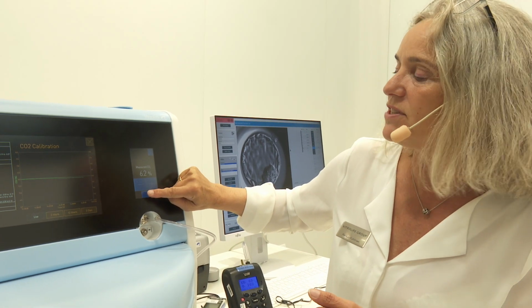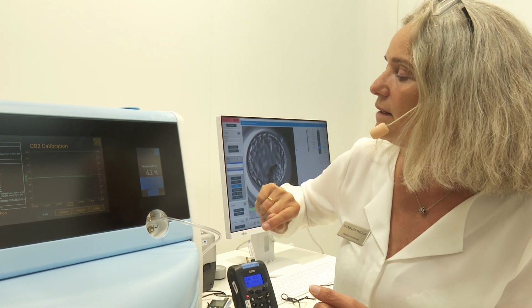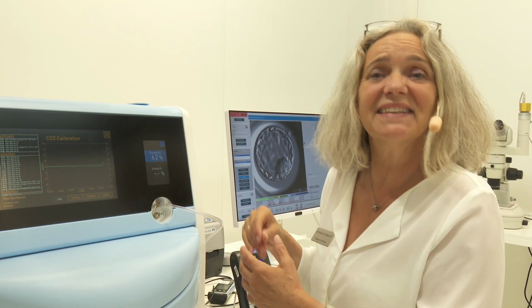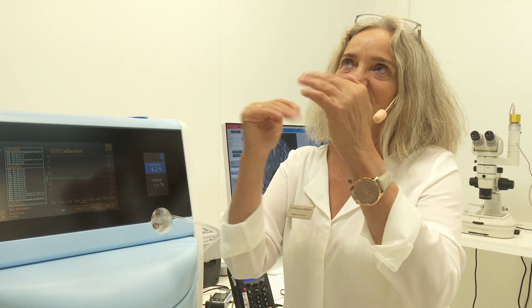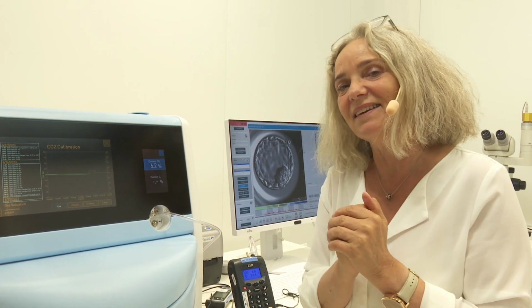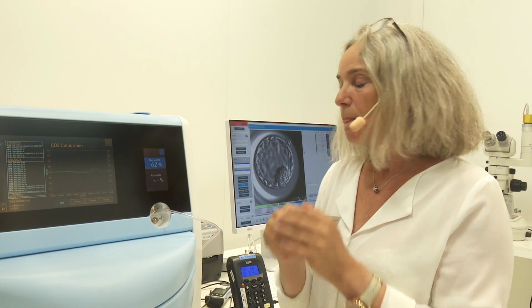And then I press on the check mark here, and then it starts calibrating. Theoretically, now it's a demonstration, I'll do a new measurement within 15 minutes, after it has stabilized and found the level, and then it should be at 6% again. Good. Normally, I do it stepwise, because otherwise you could over calibrate a little bit, and you have to go back down again. So I prefer to do it stepwise.